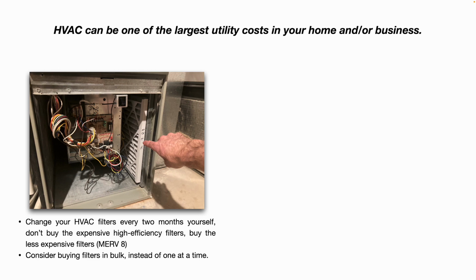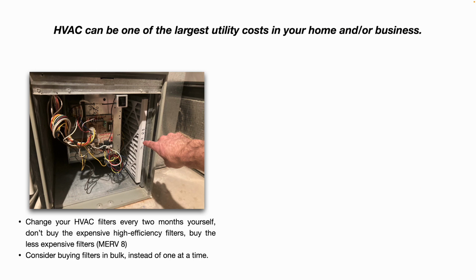And for a lot of the newer high efficiency furnaces, for example, that can cause airflow problems and cause your furnace to shut down, because when you restrict the airflow too much through a dirty filter or a high efficiency filter, it can cause switches not to close that are supposed to close when they see adequate airflow. It can cause your coil to freeze up when it's in air conditioning mode, etc.